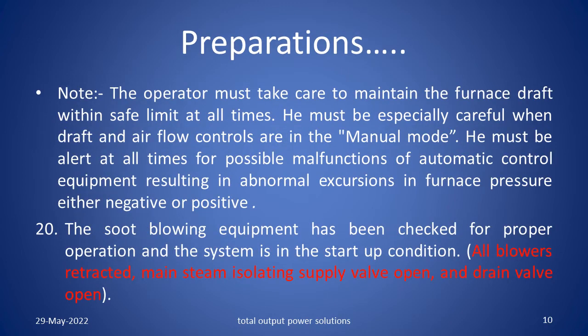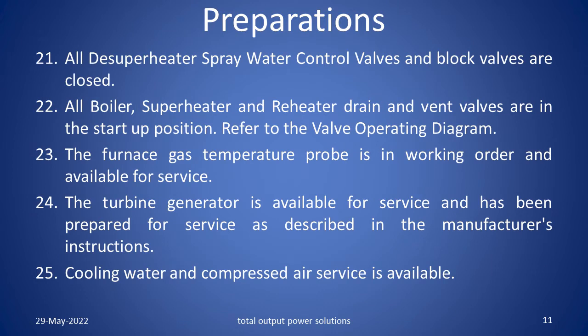Note: The operator must take care to maintain the furnace draft within safe limits at all times. He must be especially careful when draft and air flow controls are in manual mode. He must be alert at all times for possible malfunctions of automatic control equipment resulting in abnormal excursions in the furnace pressure, either negative or positive. The soot blowing equipment has been checked for proper operation and the system is in start up condition — that means all the blowers are retracted. Main steam isolating supply valve is open and drain valve is also open. All Desuperheater Spray Water Control Valves and block valves are closed. All boiler, superheater and reheater drains and vents valves are in the start up position. Refer to the valve operating diagram.